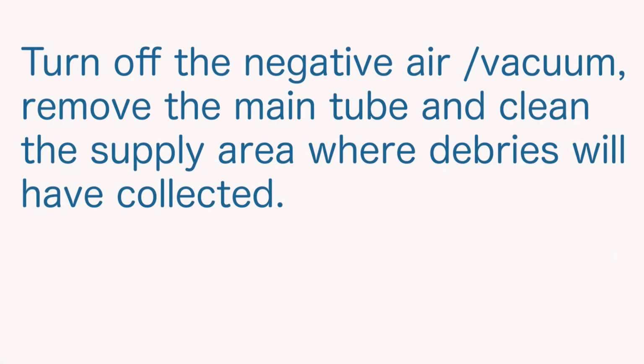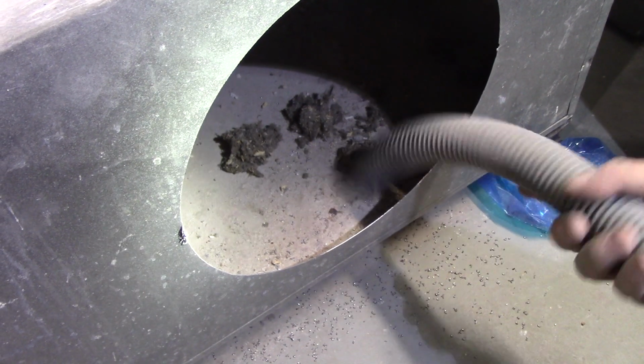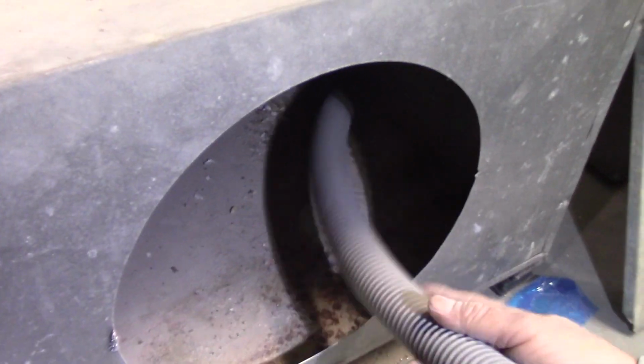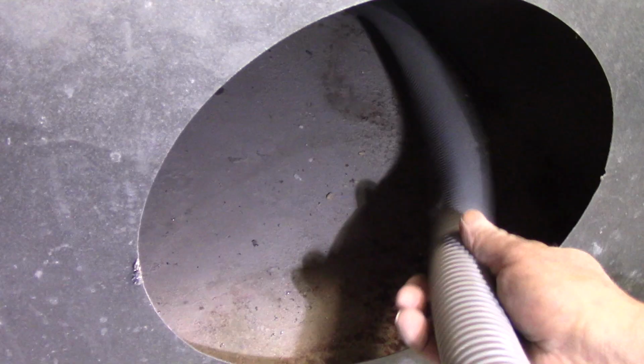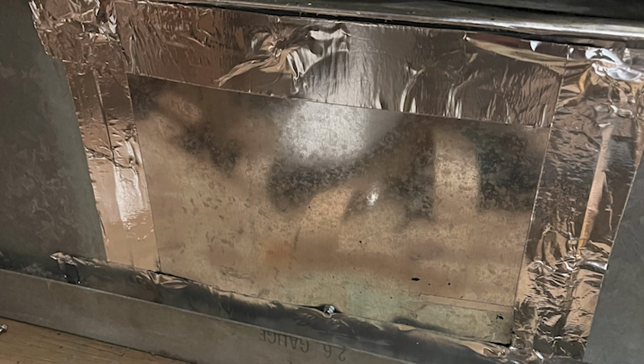After all of the supply and intake vents are cleaned, remove the hose from the main supply unit and use the shop vac to clean up the large debris that will likely have gathered there. Once the area is cleaned, use one of the aluminum sheets to cover the hole. Use the self-tapping screws to attach each corner and seal it with aluminum tape.